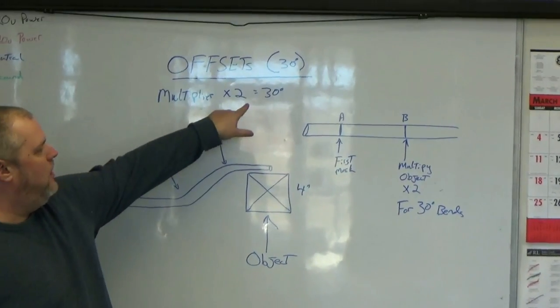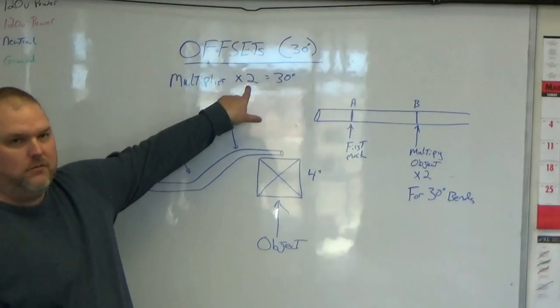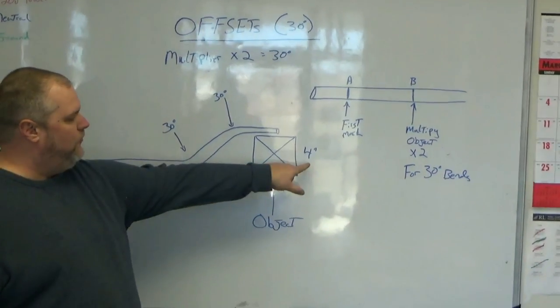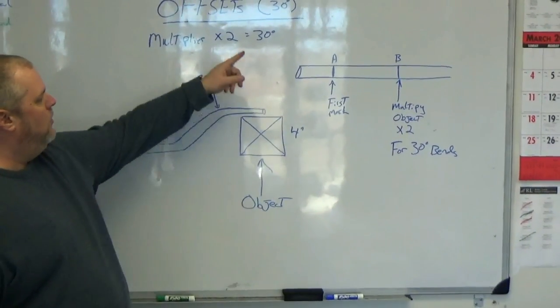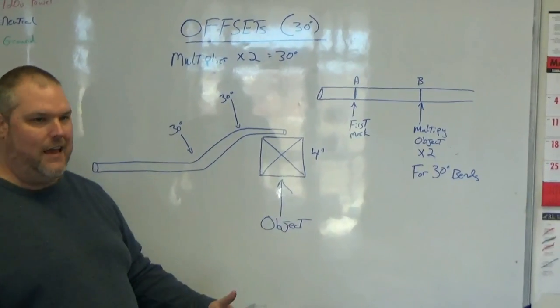Multiplier for a 30 degree offset is two. So if we have a four inch obstruction, we have to multiply the four by the two, which will give us eight.